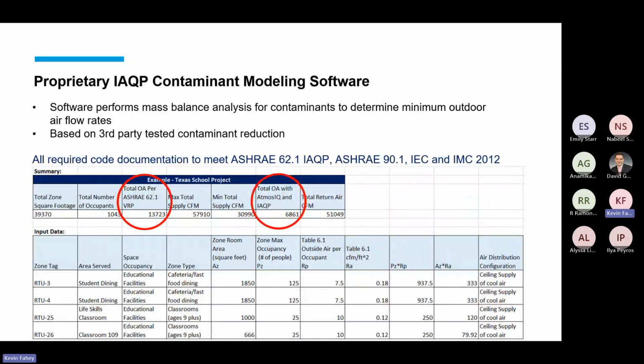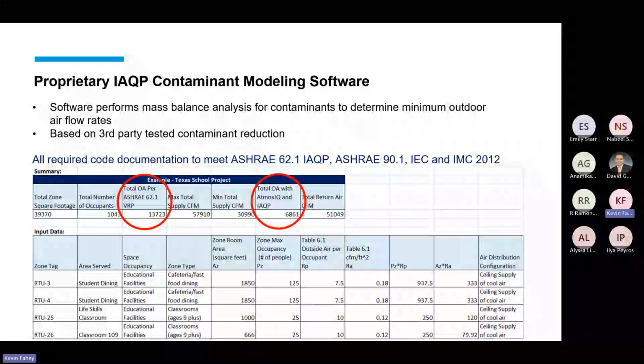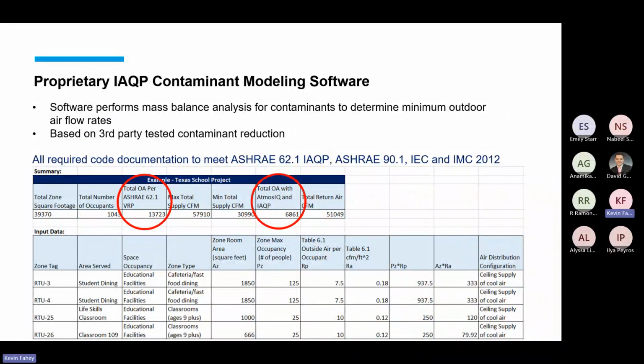But to use that, you have to do all this mass balance analysis that's part of 62.1. So what we've done is come up with a spreadsheet calculator where you enter the stats that you have for the ventilation rate procedure: the type of facility, the size of it, the occupancy, etc. Our spreadsheet will do the mass balance analysis for you and show you where you can reduce your outside air requirements with 62.1 versus using the ventilation rate procedure.